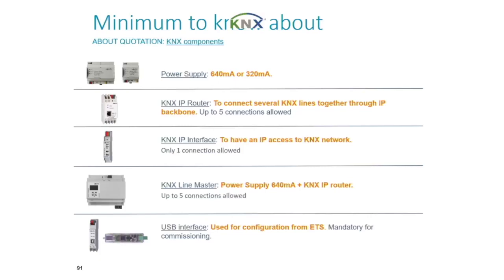A KNX Line Master is a device that's a combined IP router and power supply, so you just put one box in. We usually put a USB interface in as well. It's low tech, not networked, but it means we can turn up regardless of the state of the network and connect in with a USB cable for commissioning and maintenance. So we tend to put those in by default to make sure we've got that option.